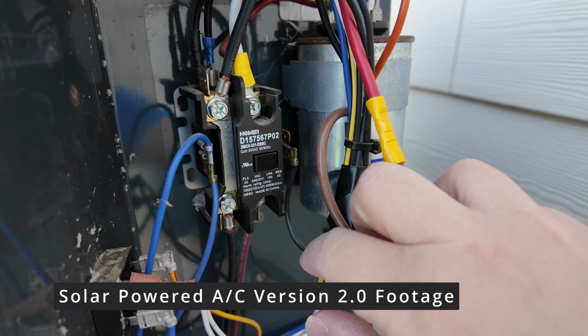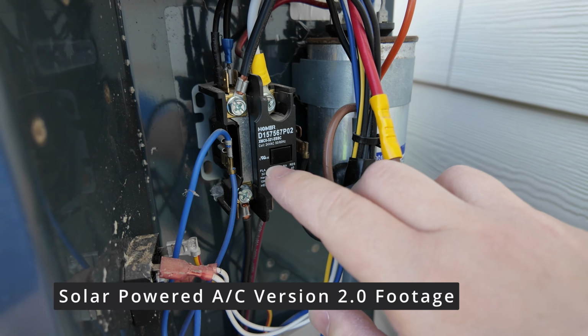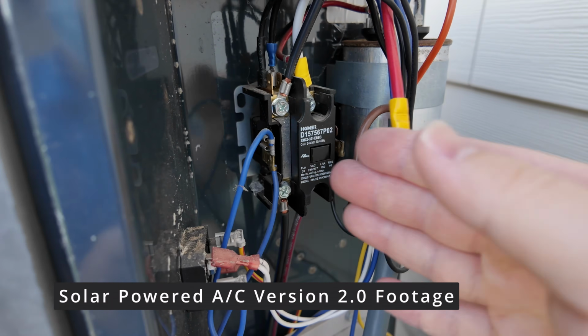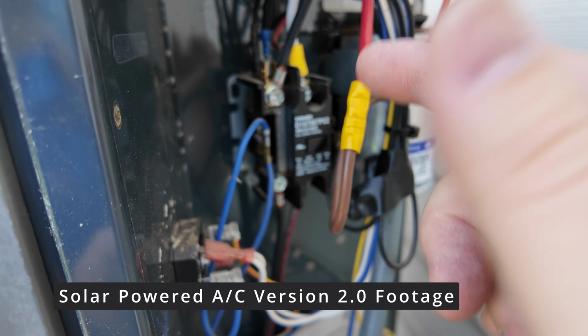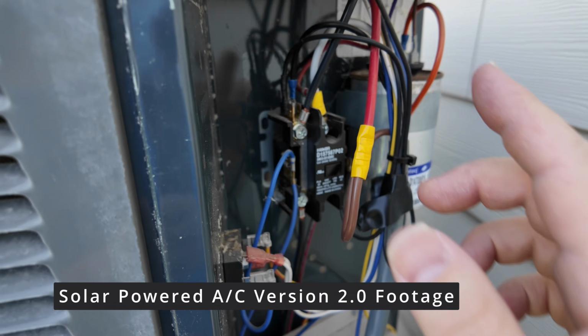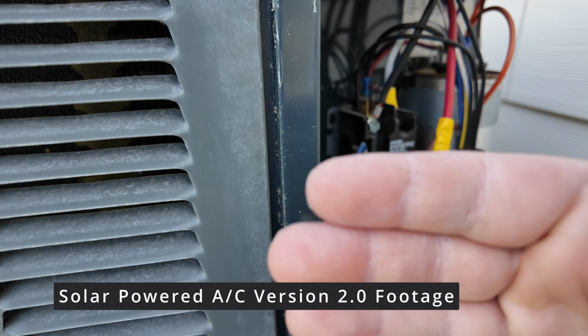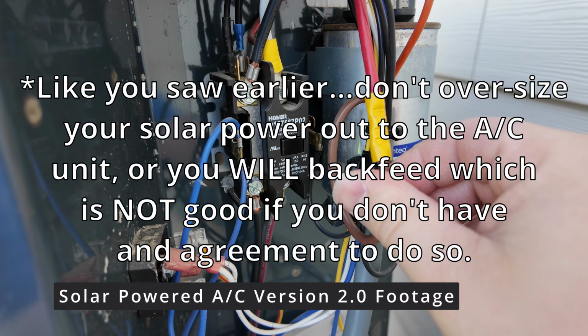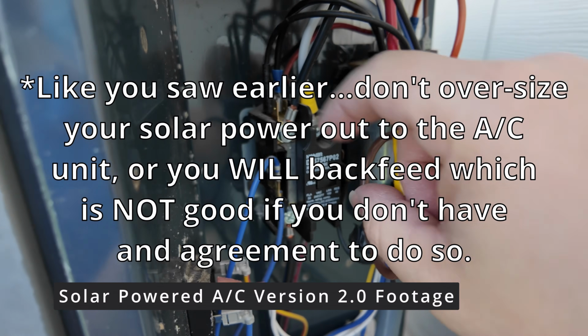We're going to use this that's controlled by the thermostat to vary when that microinverter sees the grid. So we're only accepting solar power when this air conditioner is energized. That way we are self-consuming. So we don't want to run the risk of pushing any power back to the grid. So we need to be sure and connect the solar on the top side, in my case, of the contactor. Check your flow of power.